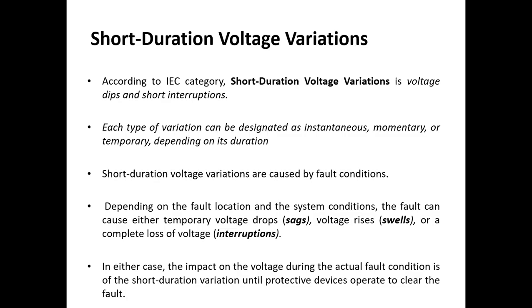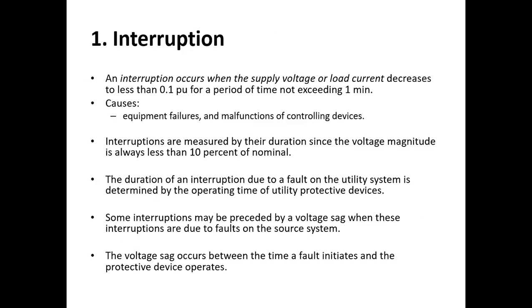Here are three concepts we need to learn. A voltage drop, in power quality terms, is a voltage sag. If the voltage rises above the normal value, we say there is a voltage swell. And many times there is a total, complete loss of the sinusoidal waveform, which is called an interruption. In either case, the impact on the voltage during the actual fault condition is a short duration voltage variation until the protective devices operate to clear the fault. So these are the short duration voltage variations.